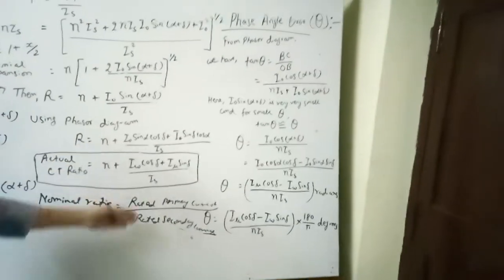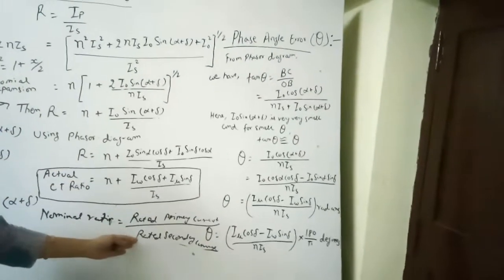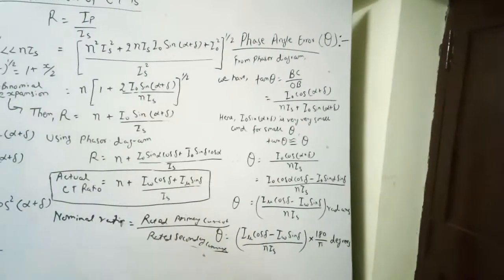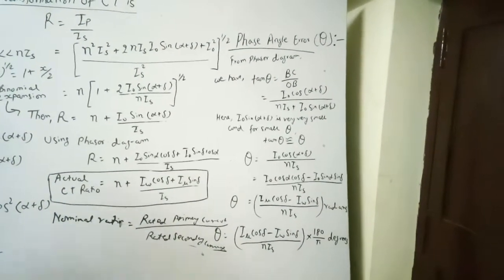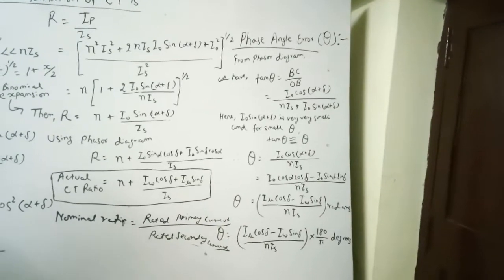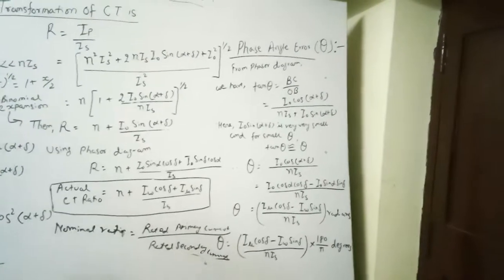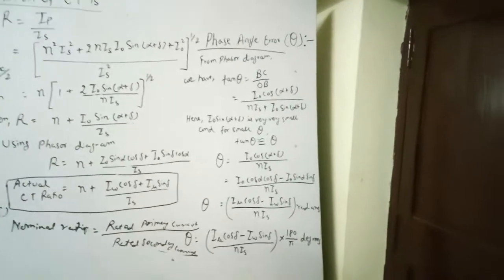From these two values — the actual ratio and the nominal ratio (rated primary current upon rated secondary current) — we calculate the percentage ratio error of the current transformer.